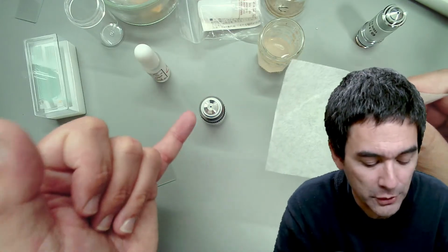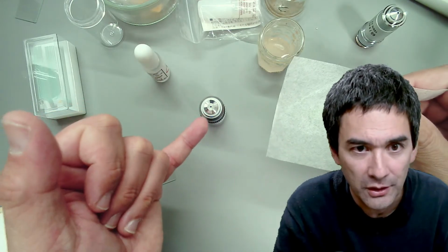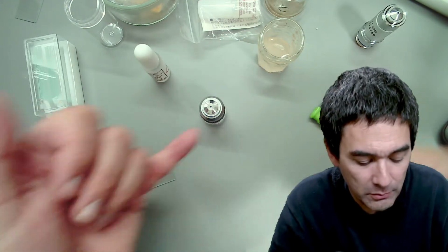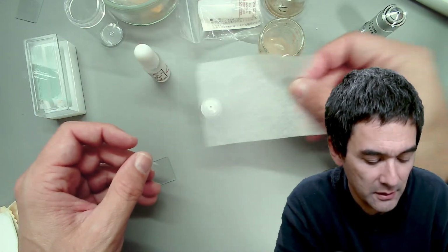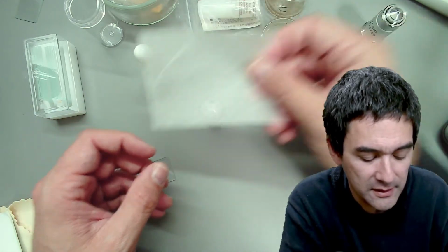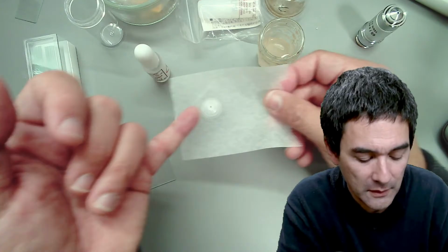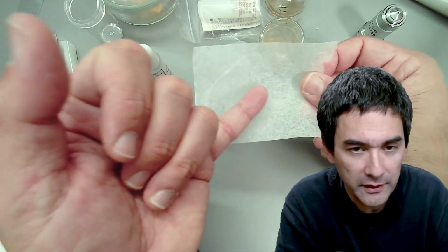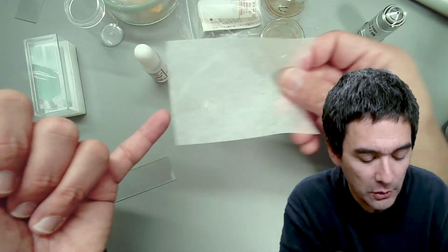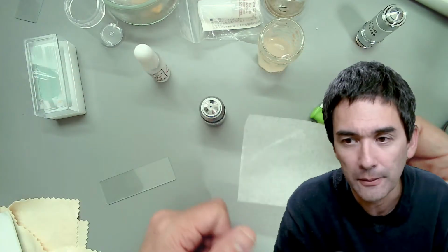Why without pressure? Because if there is any dust on here, and you start rubbing it, then you might actually make scratches on the front lens, okay? So the idea of wiping like this is to prevent any solvent from flowing in, and also to make sure that there is no pressure. Okay. Yeah.